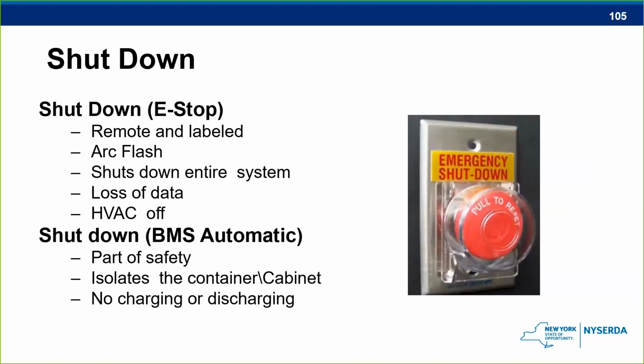And then below, we talked already about the BMS and whether the BMS should automatically shut those things down. It's part of the safety package. There's many layers of safety. There's got to be a lot to take place for these things to go south. Can it happen? Sure. The chances of it happening are slim. Can't say it could never happen. That would be irresponsible. But anyway, the BMS should actually shut these things down when it detects some sort of problem with the batteries themselves. Next slide.